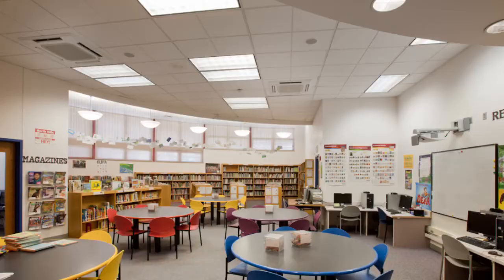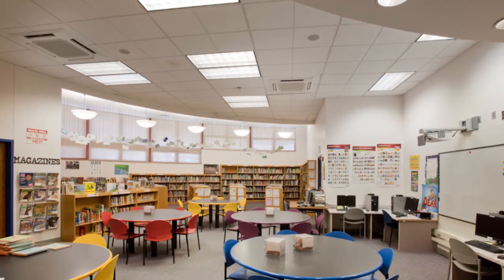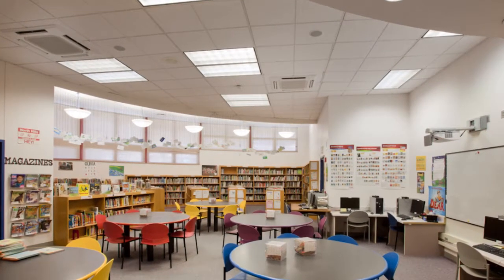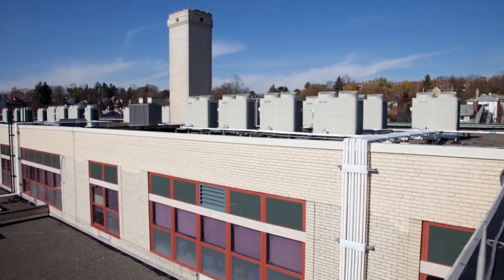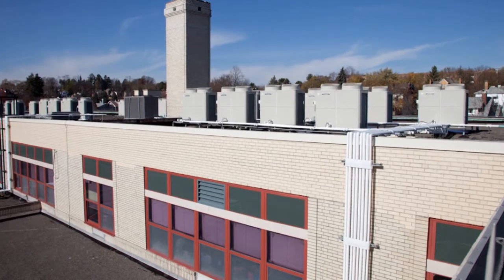Well, for this project, VRF made perfect sense. We wanted to have space conditioning through ceiling cassettes in a minimally invasive fashion. Specifically, Mitsubishi coupled that offering with a dedicated outside air offering that met our needs. What we did was took 2 or 3 classrooms and had a dedicated ventilation system complete with the energy recovery and free hot gas reheat to provide constant ventilation to each classroom in small, digestible, controllable zones.